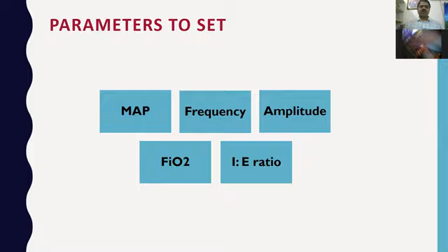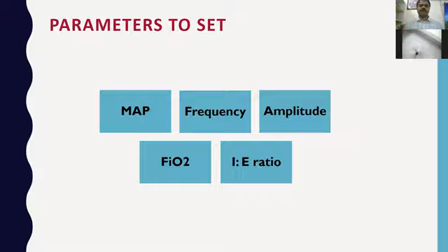So now you are done with your ventilator as well as circuit. What are the parameters to set in the ventilator? What are the parameters you have in high frequency? You have a total of 5 parameters which you need to set: MAP, frequency, amplitude, FiO2, and IE ratio.